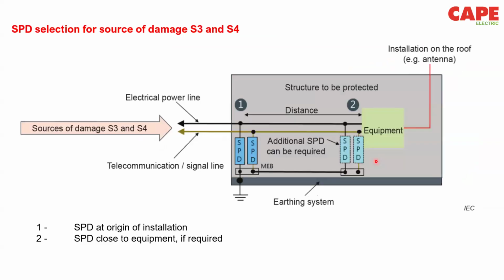And then if your risk assessment says you don't have any lightning damage to your building and your building is safe from lightning damage, then considering source of damage as S3 and S4, S3 and S4 is direct lightning strike to the power line and direct lightning strike to the nearby of the power line. We will require only one SPD at the entrance of the facility, only an SPD here. It should be at 10x350. And then if your equipment is a little bit critical, you may have an SPD nearby the equipment. That is it. No more SPD is required. So generally, it will be only one SPD for the entire installation in this case.